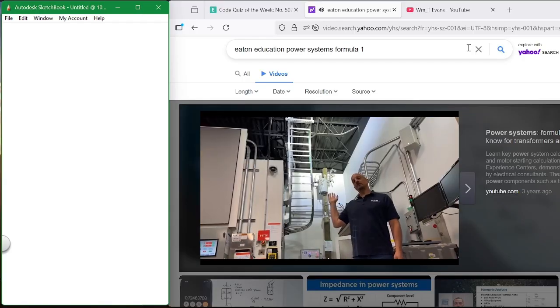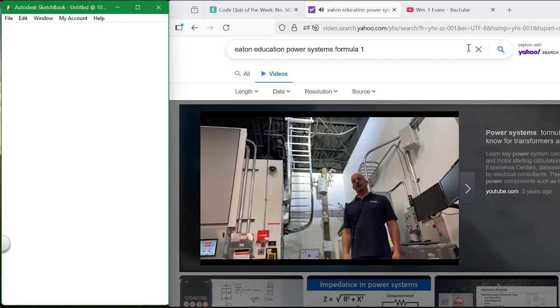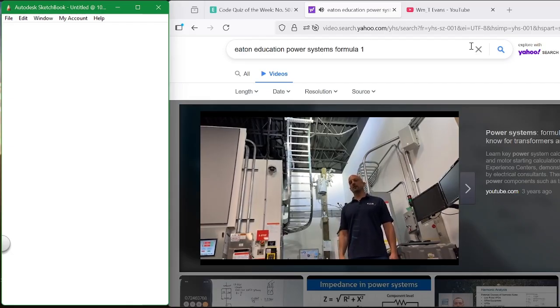Now here's a transformer on a pole. We can see it's single phase. It's 13,800 volts on the input and 240, 120 coming into your house on the output. How are you going to figure out what size that one is? Well, we can see the 10 on there. What that means is 10 kVA. But the problem is, unless I climb that pole, I don't know what the transformer impedance is.